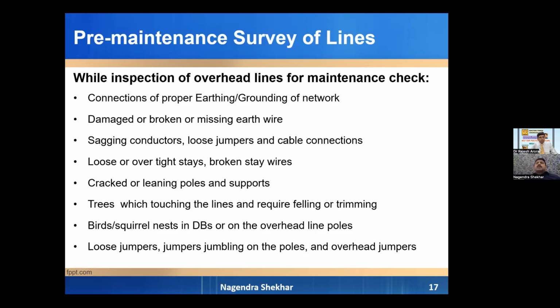Bird and squirrel nests. Squirrel nests are a new phenomenon, specifically in Delhi. When I joined this organization, squirrel nests were not found on our DBs or feeder pillars, but over time, open space is not available in Delhi, nor are trees available because of population, and new colonies have come up on farm fields. So they have found a safe space in our DBs, feeder pillars, and poles. So, bird and squirrel nests on DBs and overhead line poles, loose jumpers dangling on the poles, and overhead jumpers.